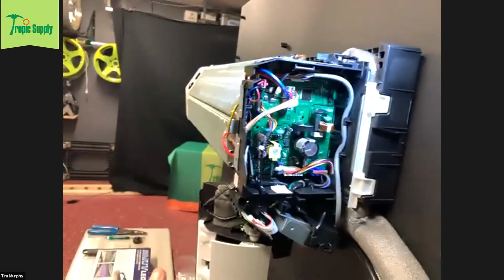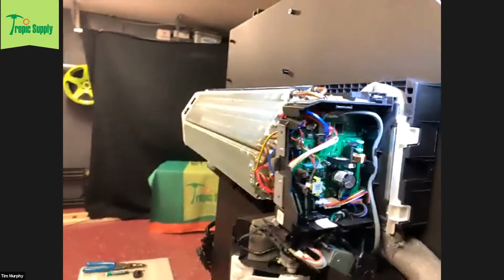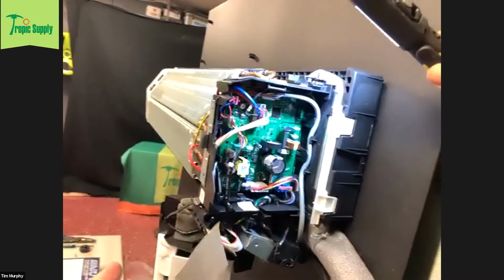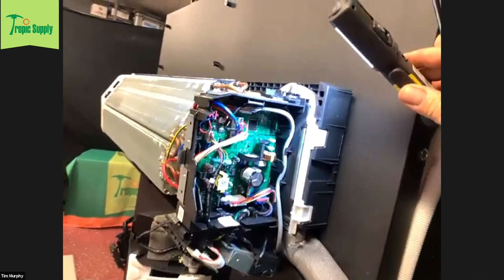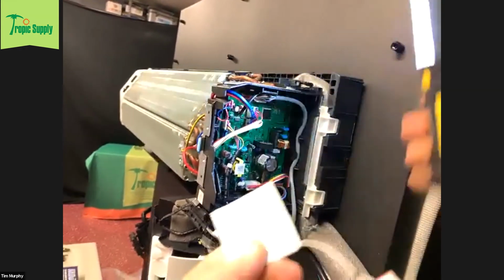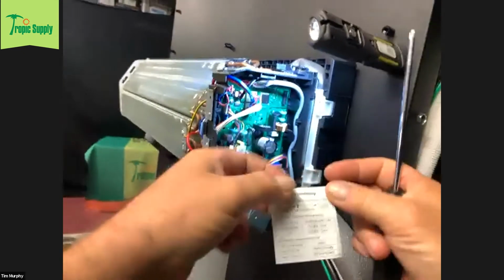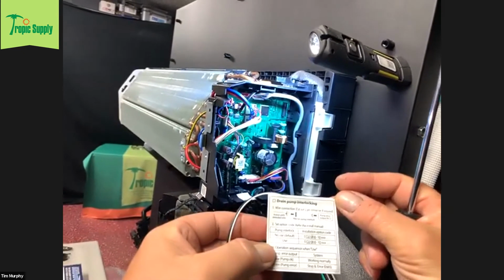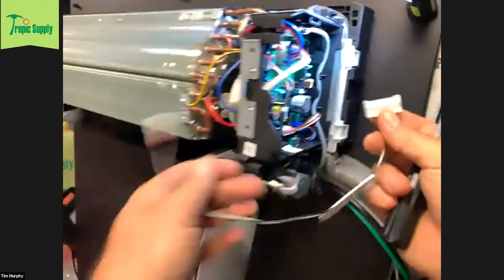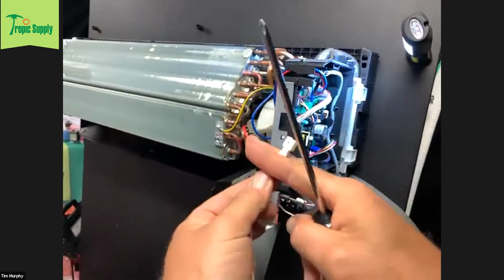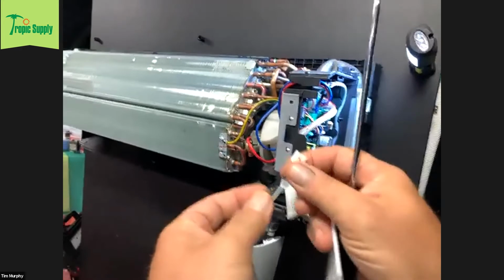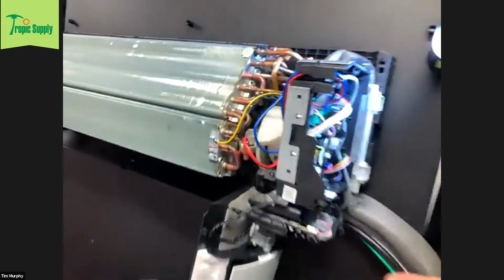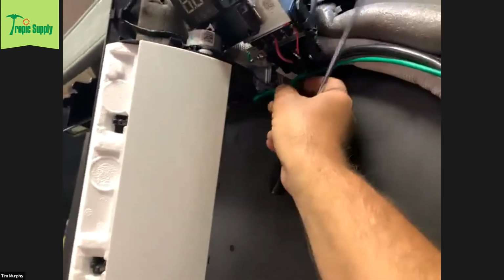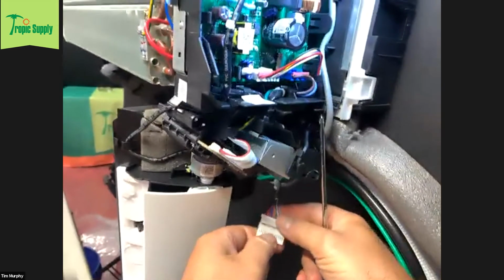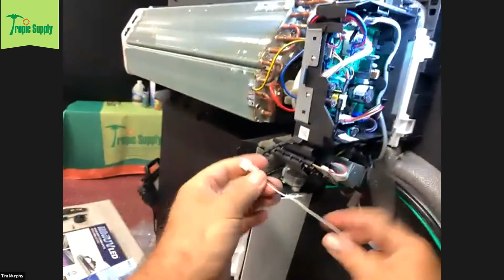Before I forget, Samsung has come up with a great way to install a float switch. On a lot of other systems, manufacturers won't tell you how to hook up an overflow safety switch. With Samsung, on the 2.0 systems, they've provided this little plug. It's a drain pump interlock. Basically, you take this harness, cut this little plug here, and this is what you're going to wire your float switch to. Any kind of overflow safety switch, you're going to break into this, and then plug that in. There's a little harness. Where is that little bugger? There's the harness here. You just take this harness and plug it in, and that's for your float switch.